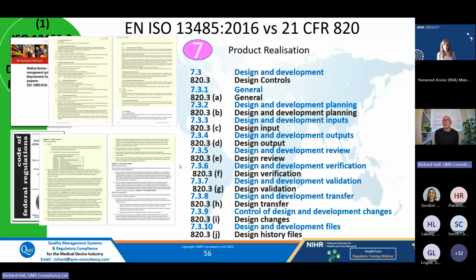So the quality management system must ensure that the product is developed within an environment that allows development and planning. Your design inputs and your design outputs have to be documented. You must do design review. You must do verification and validation of the design, and those design outputs have to be linked to your design inputs. You must have documented design and development transfer, and that includes software. You must do design and development changes. They must be controlled through the development process and afterwards once you're on the market. And design and development files are needed.